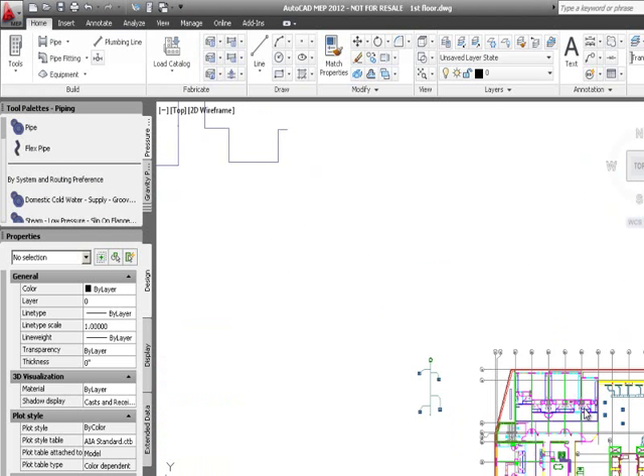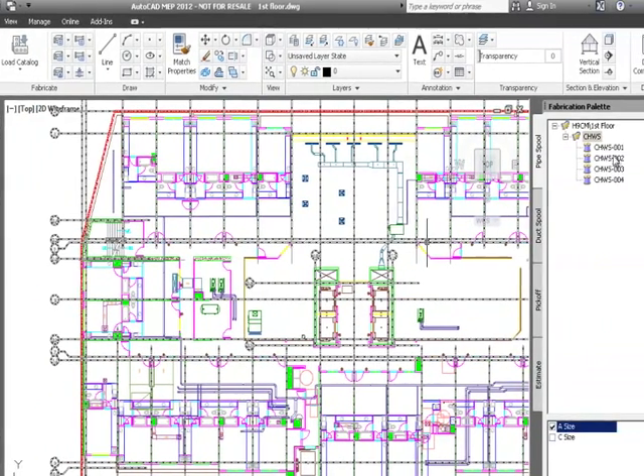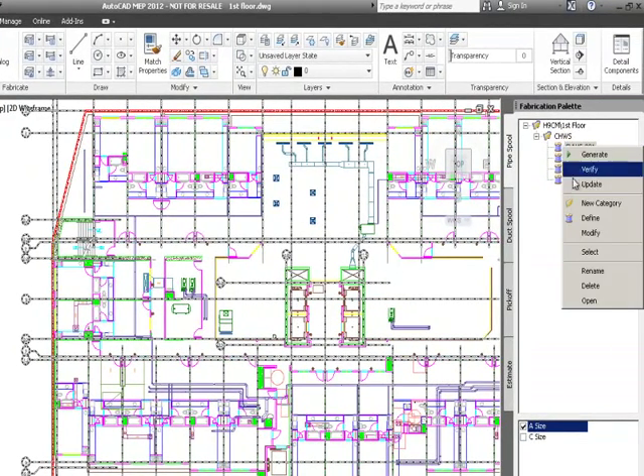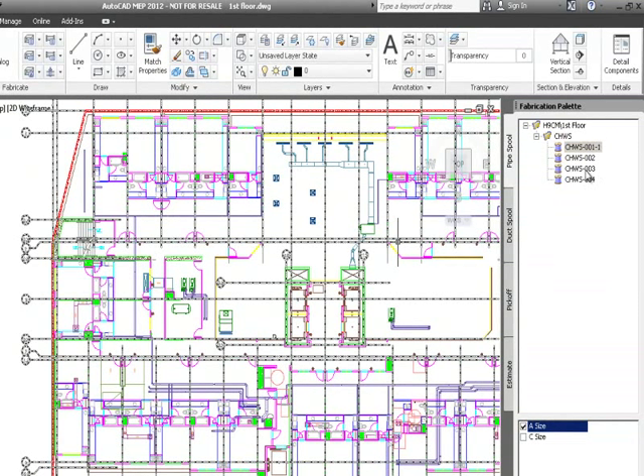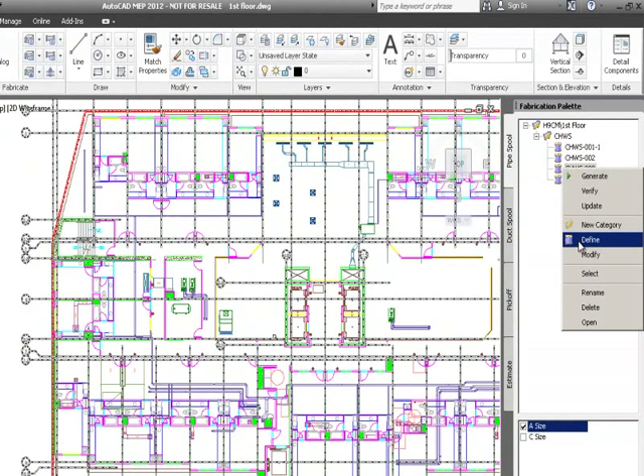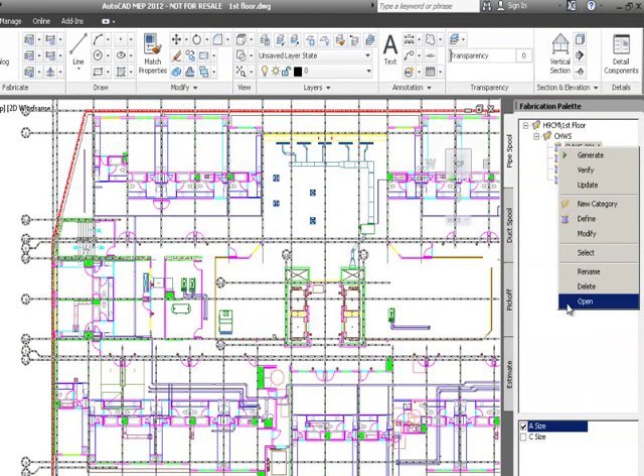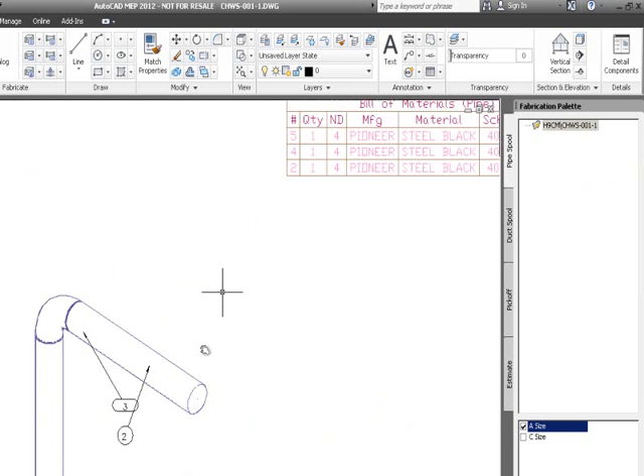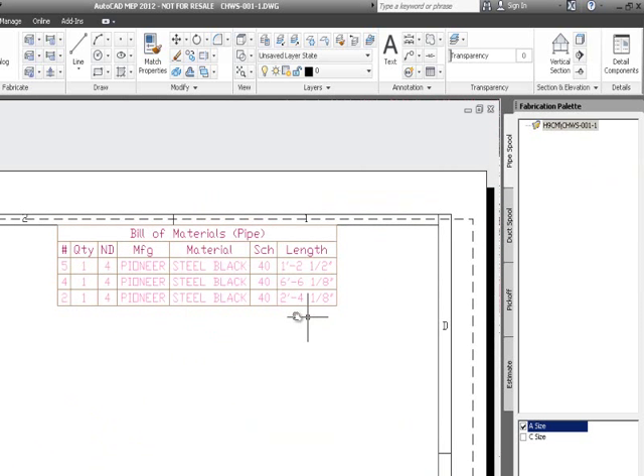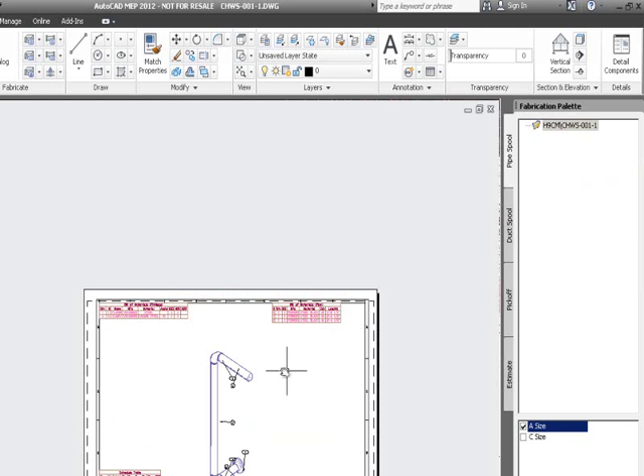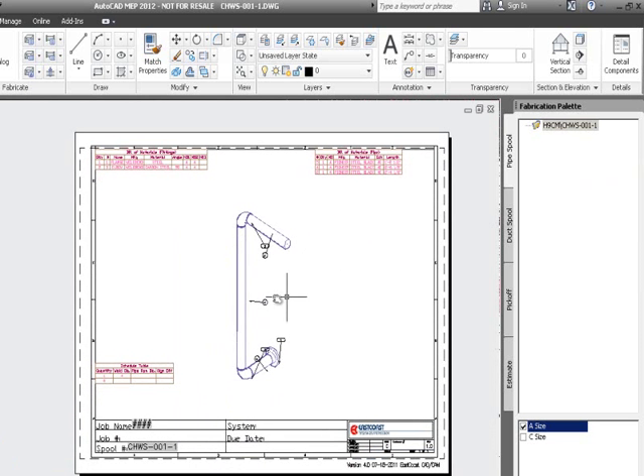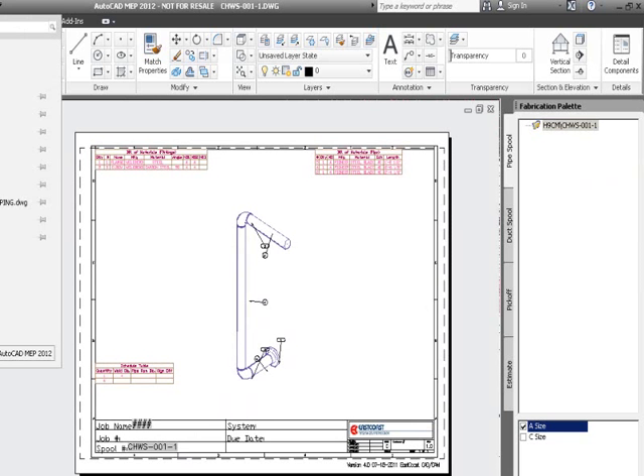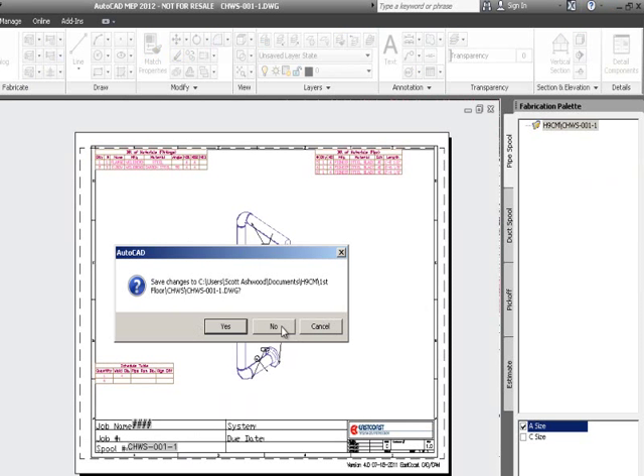I close the error log and update the affected spools. Clicking on spool one and selecting Update gives it revision number one. I do the same for spool number three. When I open spool number one again and look at part number two, it now shows two foot four and one-eighth, updated to reflect the change made in the model.